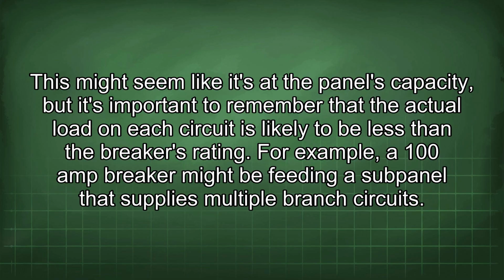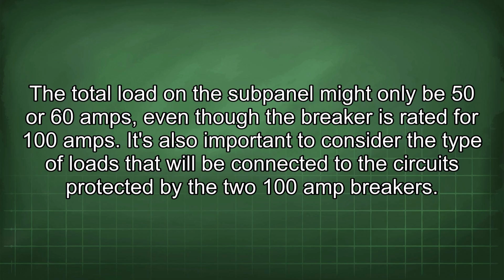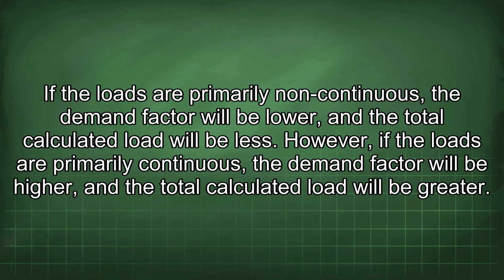For example, a 100-amp breaker might be feeding a subpanel that supplies multiple branch circuits. The total load on the subpanel might only be 50 or 60 amps, even though the breaker is rated for 100 amps. It's also important to consider the type of loads that will be connected to the circuits protected by the two 100-amp breakers. If the loads are primarily non-continuous, the demand factor will be lower and the total calculated load will be less. However, if the loads are primarily continuous, the demand factor will be higher and the total calculated load will be greater.